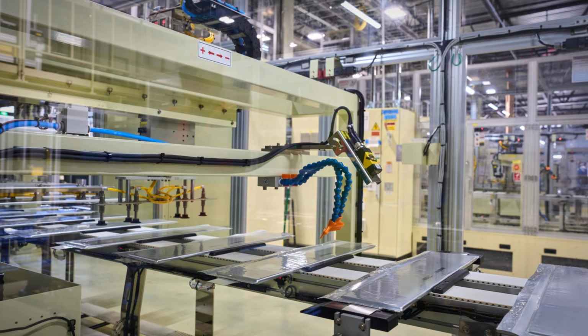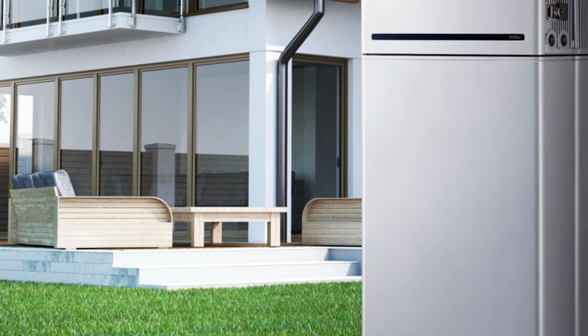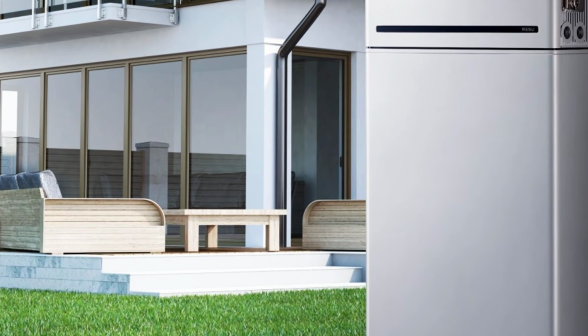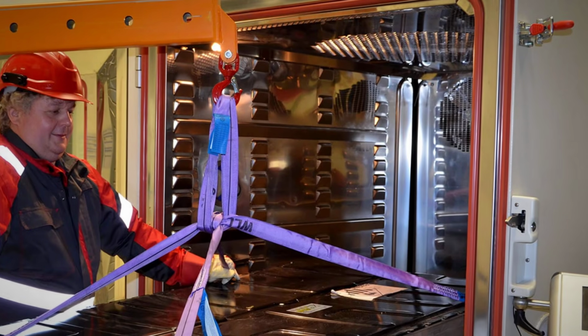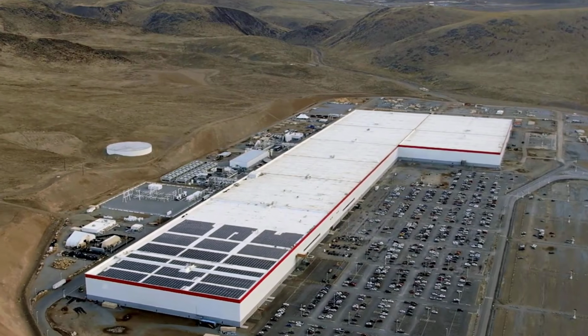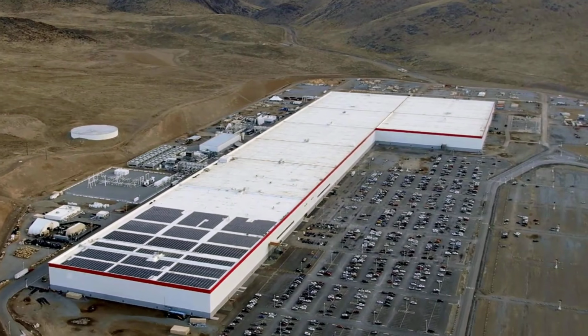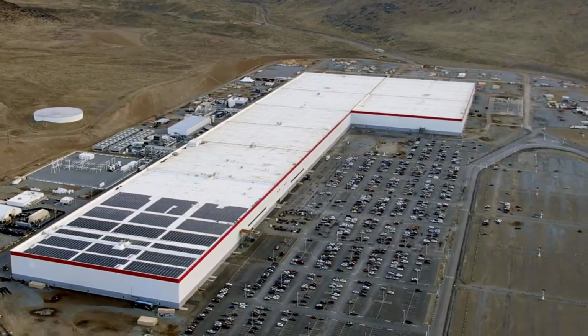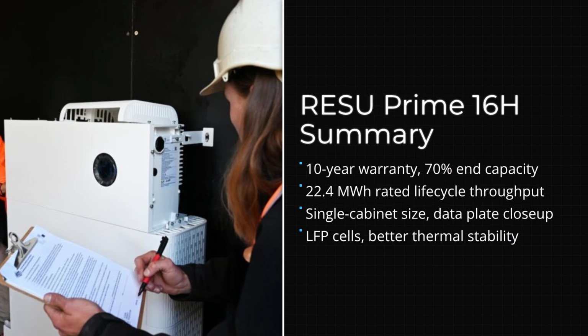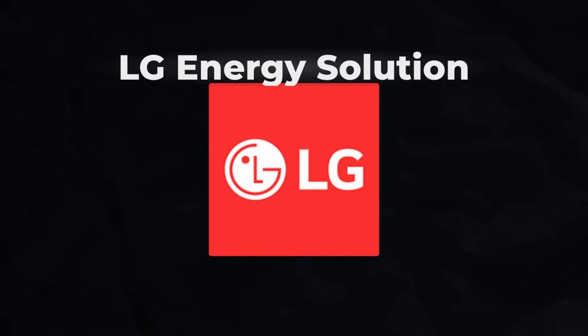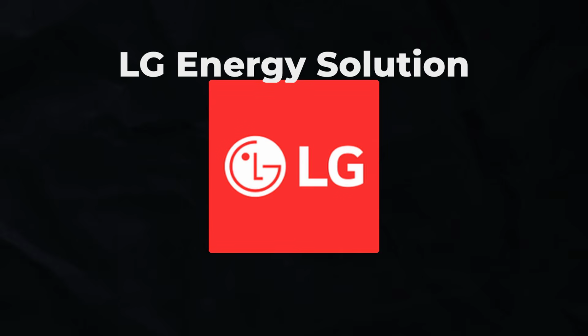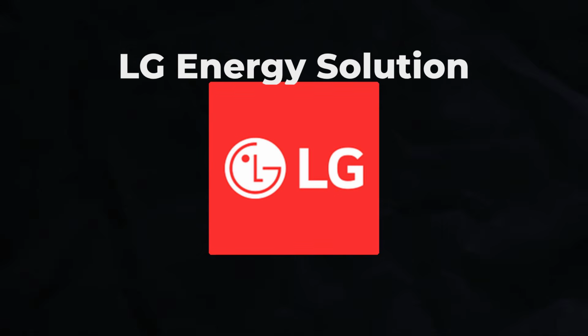It moved off the older nickel-based chemistry that LG's earlier RESU line used over to lithium iron phosphate in this Prime generation, which is the safer, more thermally stable choice, and the same direction every serious battery maker on this list has gone. The warranty here is 10 years, 70% retention, rated for 22.4 megawatt hours of total throughput. That's solid, not class-leading, but backed by one of the largest lithium battery manufacturers on the planet.